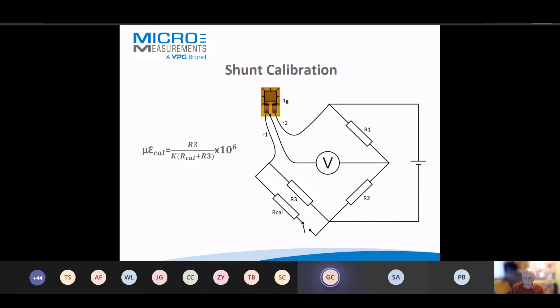A lot of what we talk about with instrumentation is using dedicated instruments. Although you can go to first principles and build something yourself, dedicated instruments do all of this for you, including bridge completion and shunt calibration circuits with the maths to cope with that. There's also variable bridge excitation - a small gauge on plastic or composite would heat up a lot more than a large gauge on a piece of aluminium, so you might need variable bridge excitation in your instrumentation.